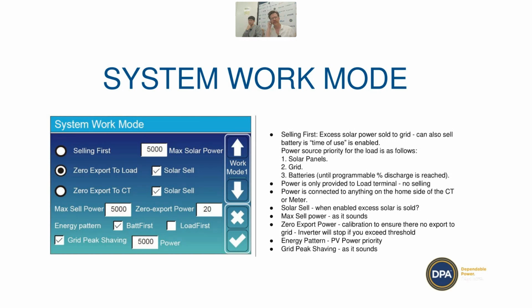customer, and you get fined for exporting even a little bit out to the grid, then you might set zero export to 20 watts or 100 watts or something, so that you're always pulling 20 watts to make sure that you're never actually exporting. So for most residential applications, that's not going to be a problem.